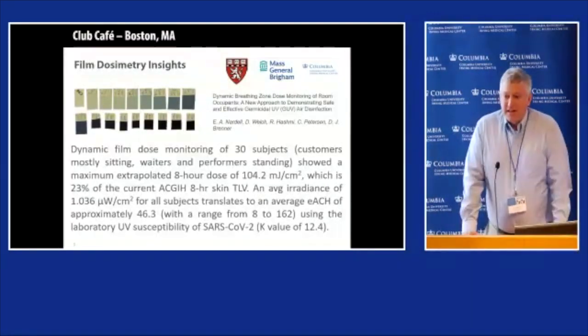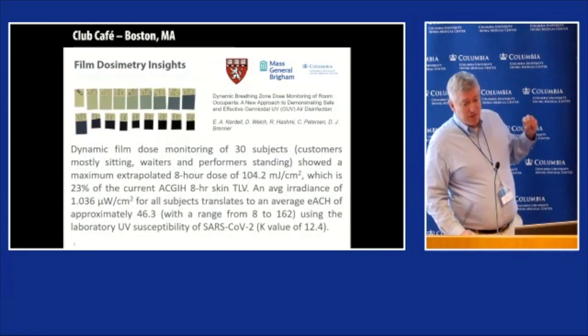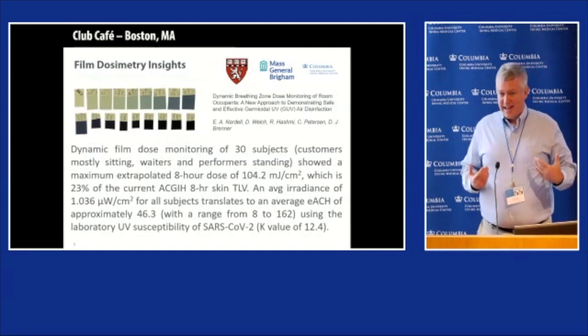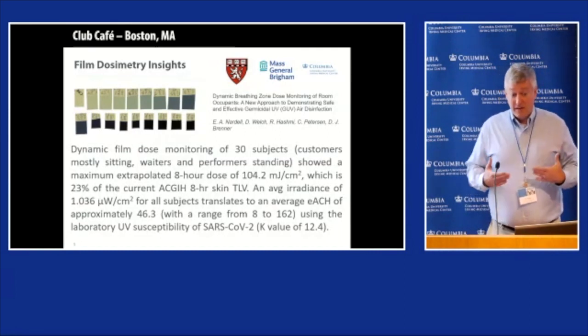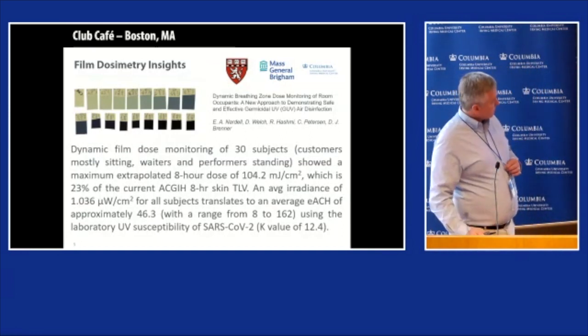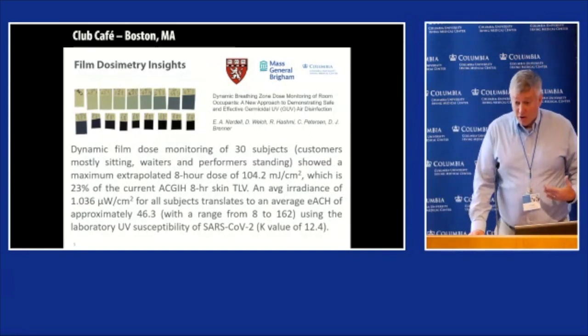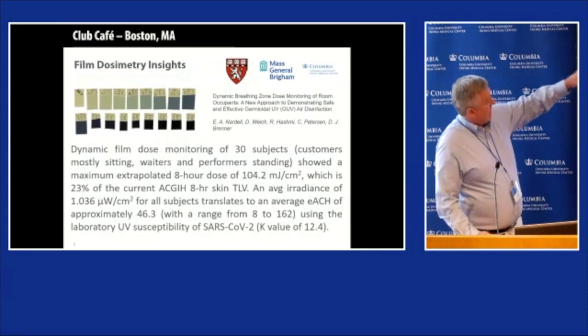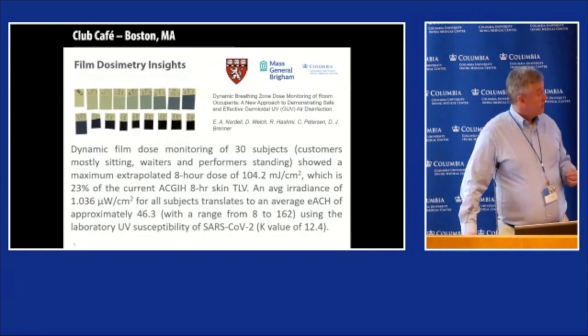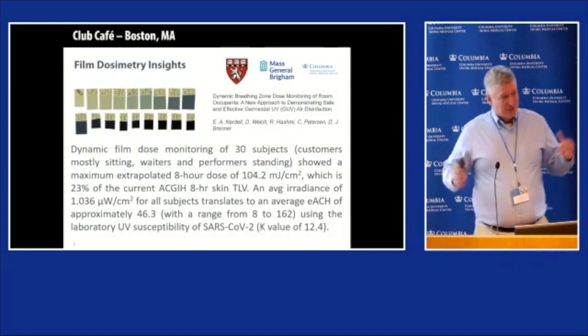Columbia and Ed followed up with film dosimetry to measure how much dose subjects actually received—this is more of a safety-related measurement that takes into account time-weighted averaging. Within 30 subjects, we saw that somebody sitting gets less dose, and somebody standing gets a higher dose. We got pretty close to our target of 50 equivalent ACH according to this study.